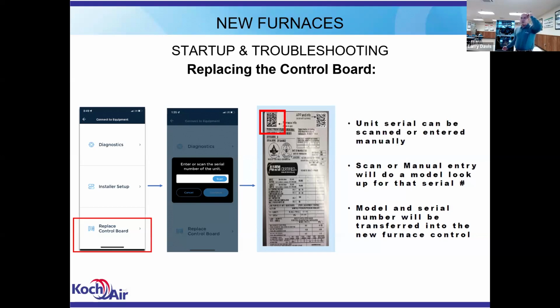Well, that's later on. You can try scanning the board to pull up its settings. Okay. And then just program your new board to those old settings, plug it in and you're done. A lot of times, if you're changing a board because it's smoked or trashed or broken, it's always worth a try to see if you can pull that information up. But just know that if you can't, it'll load the default values on there. That's where that report comes in handy. You can just change the values you need to and set the board and put it in and go.